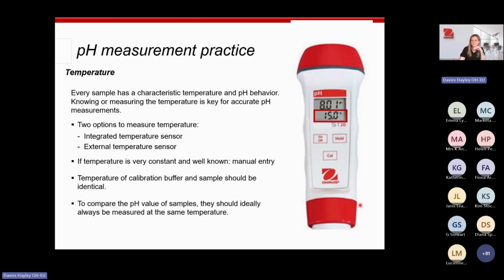Generally, they are set to around 25 degrees, but if it's anything different to that, you can manually enter the temperature into the meter, and then it will use the built-in algorithm to determine what the pH is based on that temperature. If you've got an integrated temperature sensor, then that will work it all out for you. And you'll see on this one here, it has the temperature showing as well as the pH value. Again, make sure the temperature of your calibration buffer and your sample is identical, just to make sure they're measured at the same temperature.